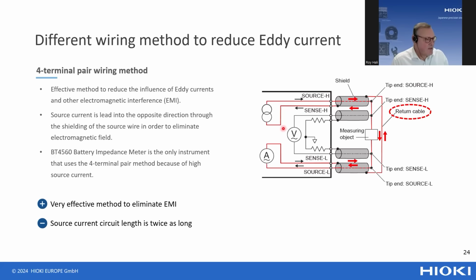The principle is like this: you have your same AC source, and the AC source first goes through the core wire of the coaxial cable, then flows through the battery, returns to the instrument through the other core of the coaxial cable, but then it returns again through the shielding of the coaxial cable. As you can see here, because of the opposite directions of the current, the magnetic flux resulting from the measurement current is cancelled out.